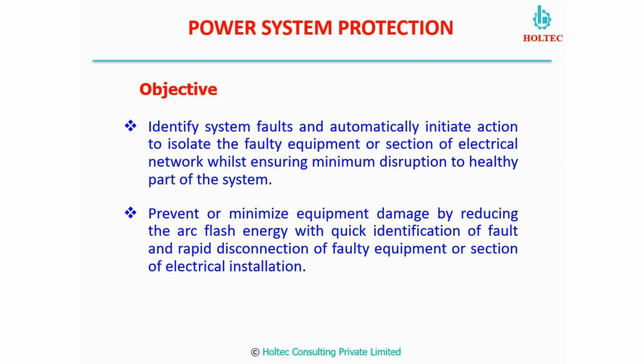This protection system will prevent or minimize the damage in the system, right? Why? Because we are reducing the arc flash energy with quick identification and rapid disconnection of the faulty equipment or section. So in that way, we are either preventing the damage or minimizing the damage in the equipment. It is not 100% sure that if your relay works perfectly, there will not be any damage in the equipment. No, it is not like that. When there is a fault, definitely some damage has already occurred in the system, but we can minimize that damage. There are some cases like overloads or under voltage or over voltage conditions. If these kinds of protections operate, then we can even prevent the damage of the equipment. So it is not that in 100% of cases it is ensured that if equipment protection is operating, we are saving the equipment from damage.